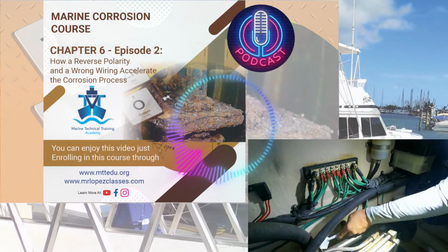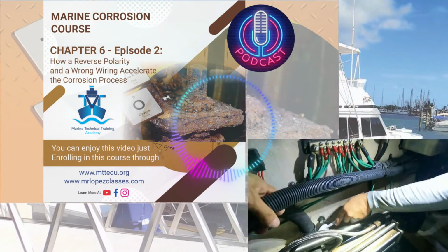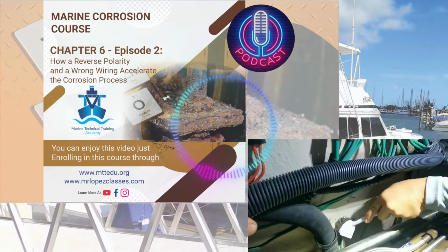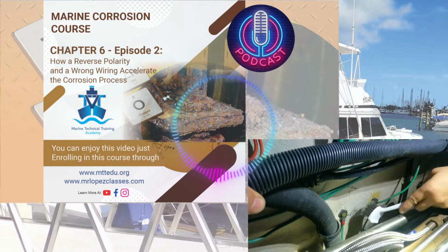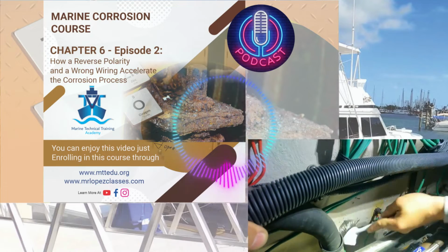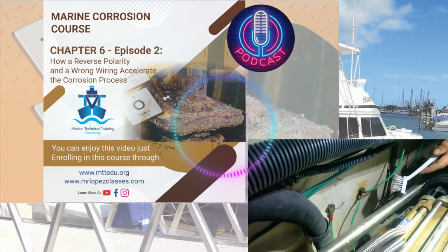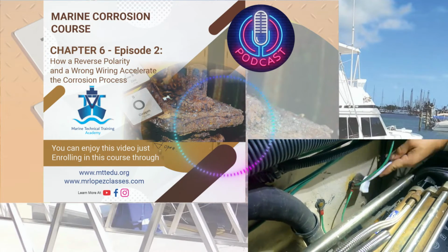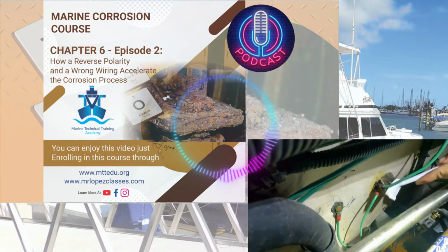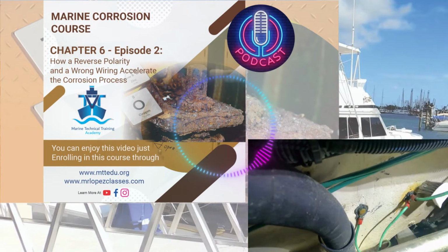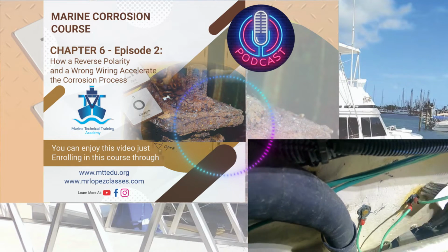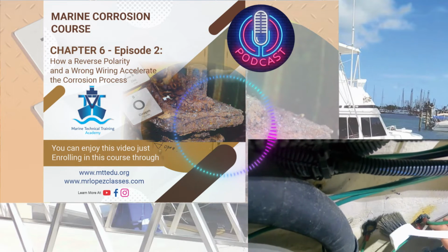The red one is solid, is on. This is an indication that you have reverse polarity. This is an indication that your neutral bus bar in this moment is hot. My neutral bus bar is hot. Once again, but everything is working. Yes, everything is working, but it's not good. I am going to explain right now why it's not good.